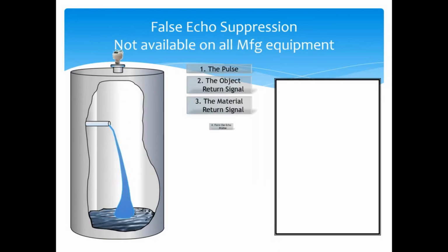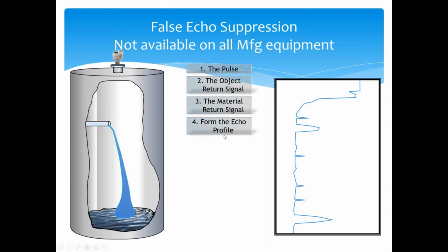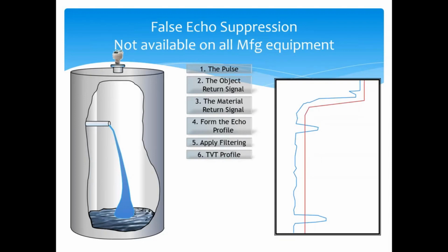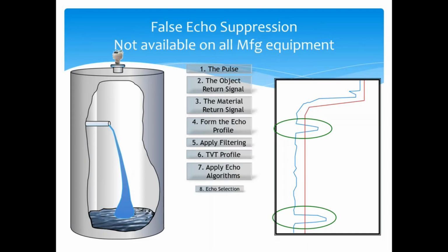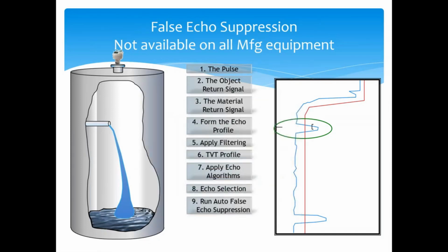So the same thing that we talked about earlier, you have the pulse, you get your signal return, you're forming that echo profile, we do our filtering, apply our TVT profile, apply our echo algorithms, but which one of these should we pick up on, the fill pipe or liquid level below it? Well, if we run an auto false echo suppression or a mapping, we can actually map out that fill pipe. So you want to run your auto false echo suppression when liquid level is as low as possible in the tank, so we can see any obstructions that might be in there. And what we would actually do is set the range value from the face of the transducer, how far down in the tank we want to run it, and then that becomes our suppression range that we learn. So we would reapply our TVT filter, and it would contour above this fixed obstruction. So that's how mapping works to ignore any sort of fixed obstructions inside of a tank.